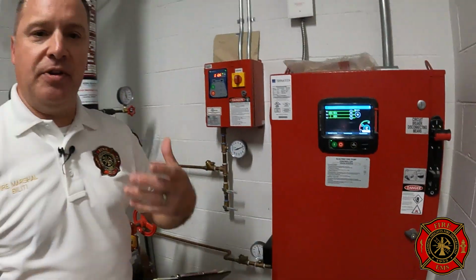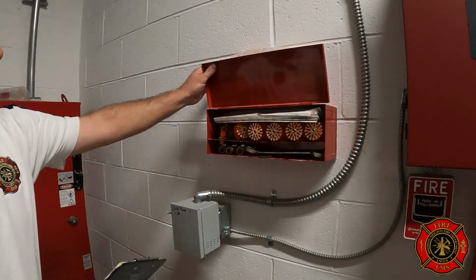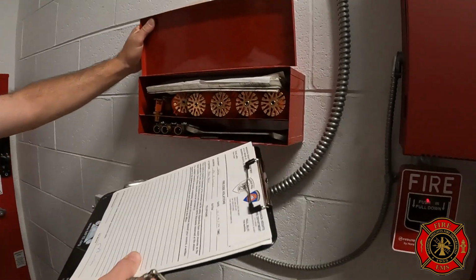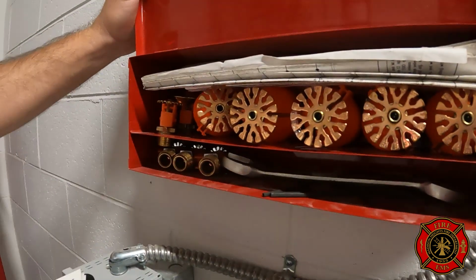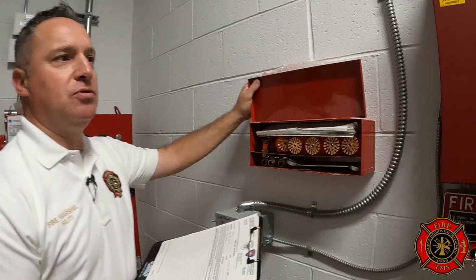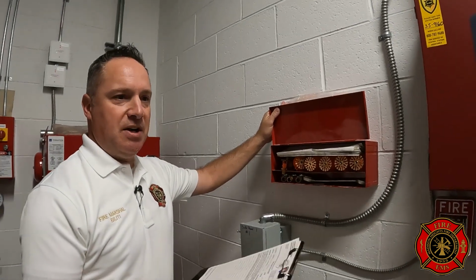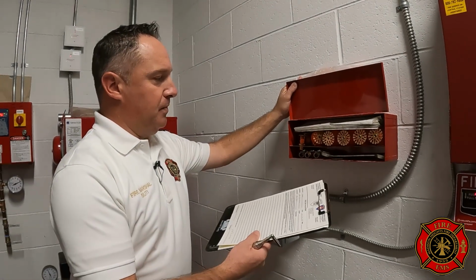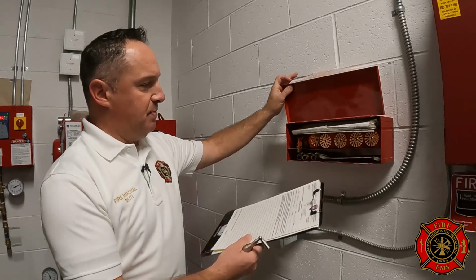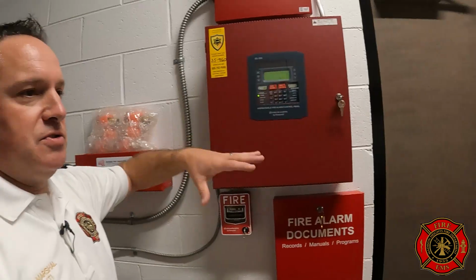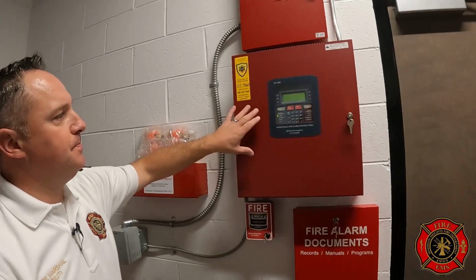So by cycling that, I know that the pump is still working. Another thing that I look at is making sure that they have spare sprinkler heads inside there. So if an accidental piece of equipment hits a sprinkler head and busts one off, we have spare sets on site. This room also houses their fire alarm system.